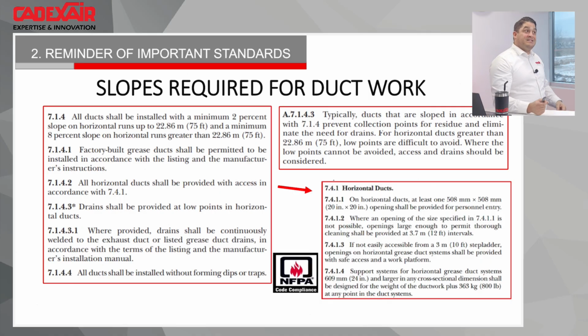So we were on site, and I said to the engineer, okay, you will go in and wrap it out from one point to the other point. So yes, it's in the code. Maybe if your ductwork is like 60 inch by 60 inch, that's not a problem. But as soon as it's 20 by 20, I found it a lot more difficult to do. And also if you do that, you have to take into consideration confined space workplace rules, so there is a ton of security to add to that. I will say it's not something we suggest, so we prefer to have a lot of regular access.